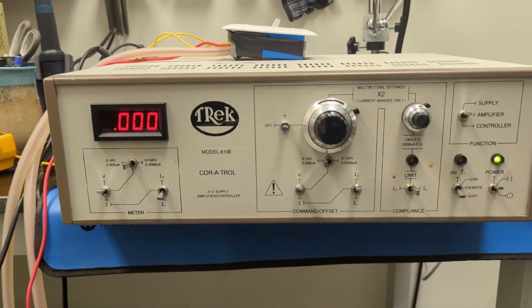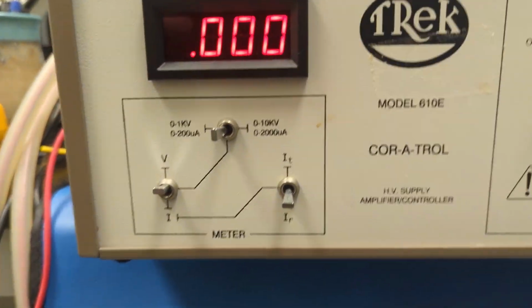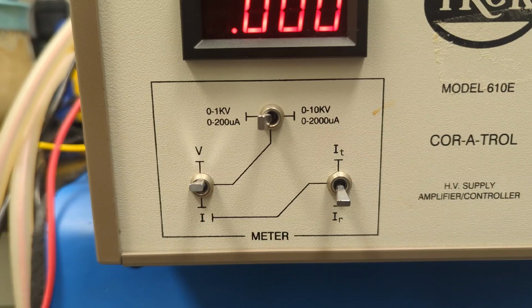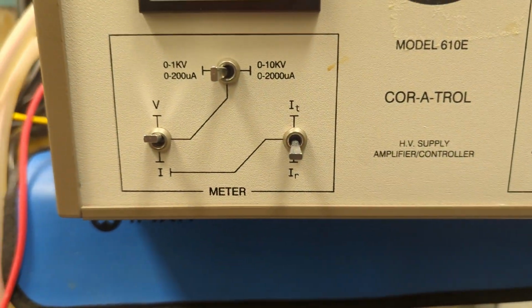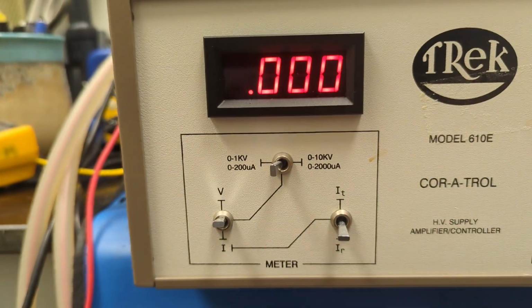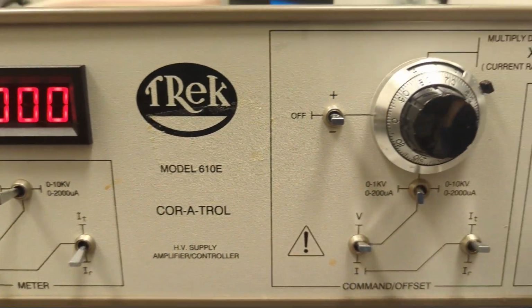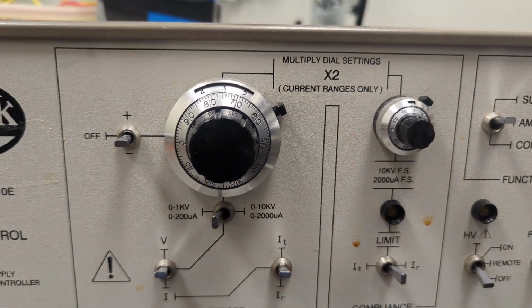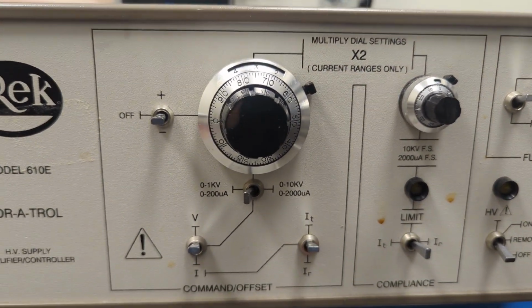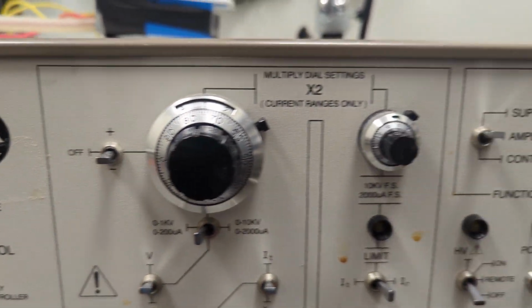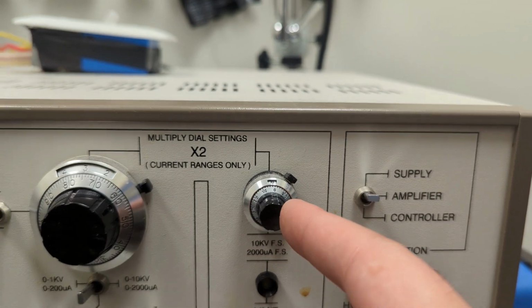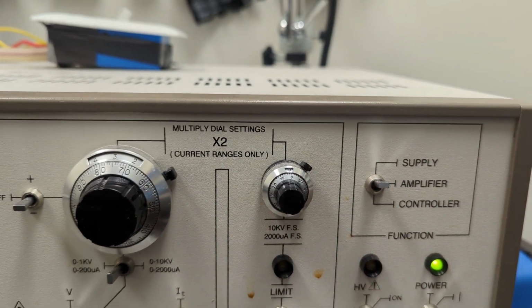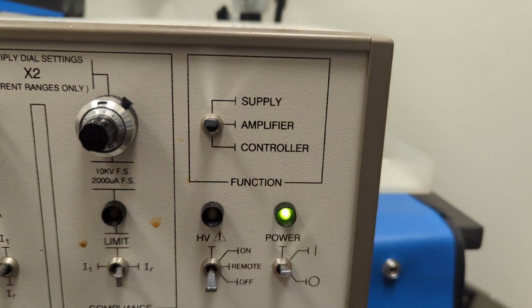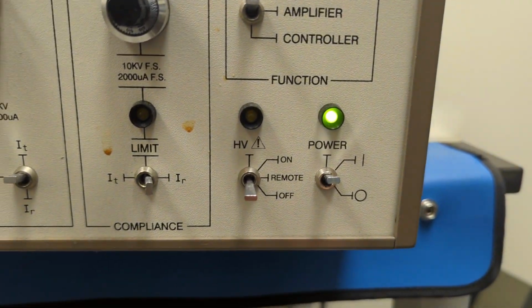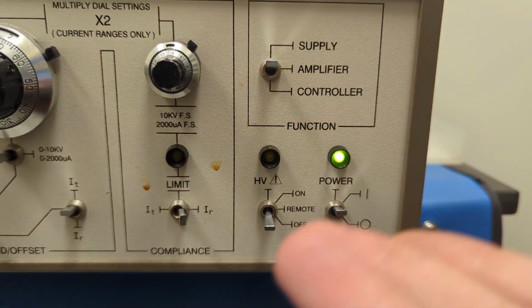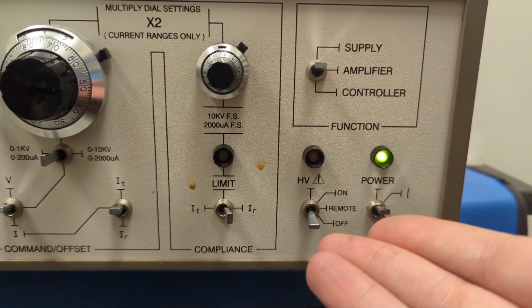But yeah, so it's got this 3-digit display, and you can see here it's got these two settings. One for 0 to 1 kilovolt, one for 0 to 10 kilovolt. You've got your choice for the meter, at least you can read in volts and amps. This controller here is to set your voltage or your current. You can change the polarity here with that switch. And this is basically a limiting switch, current or voltage depending on what setting you're in. And then of course you have the function switch here, and then the high voltage switch to turn that on. You can also turn it on remotely as well.